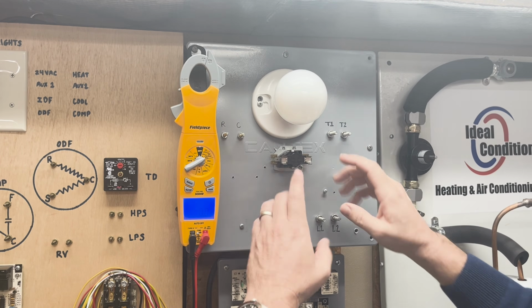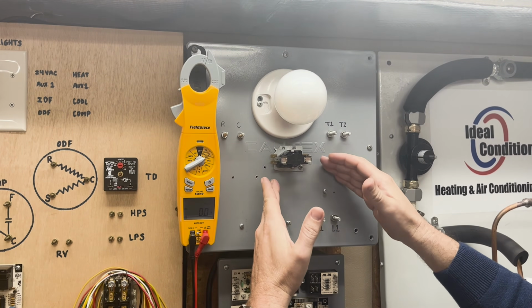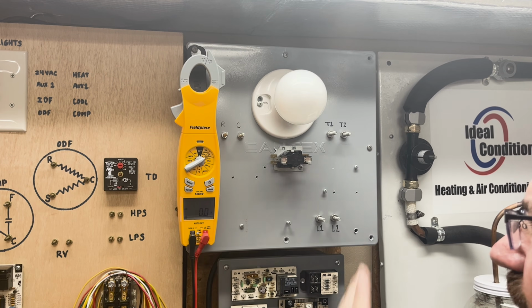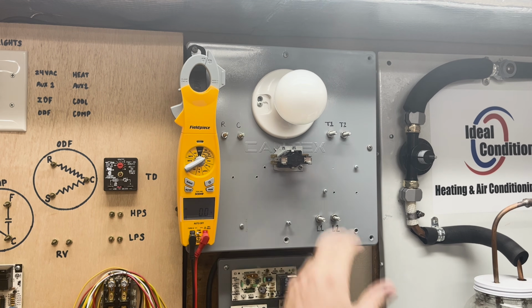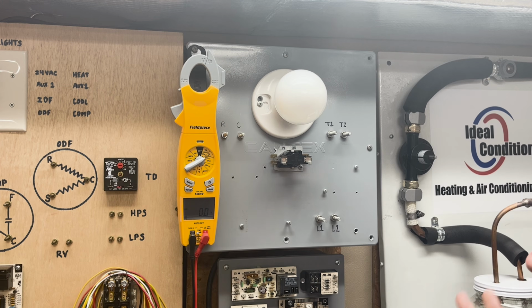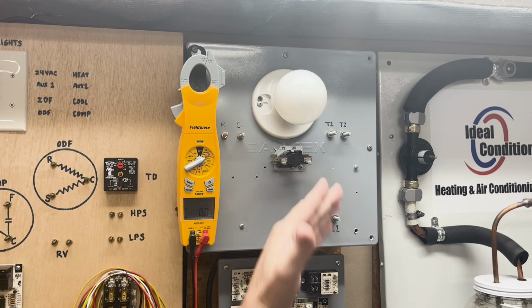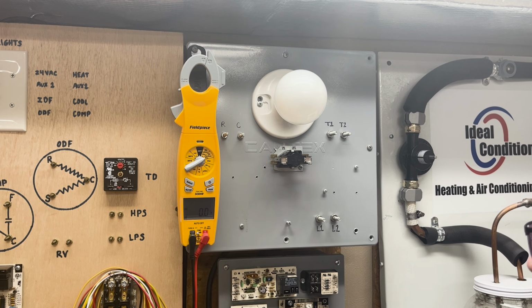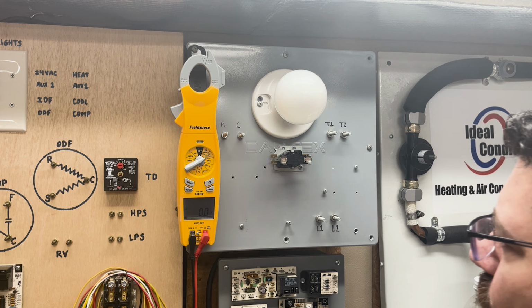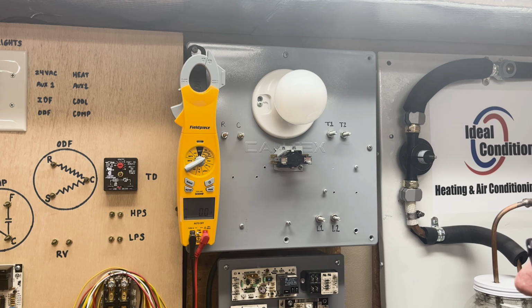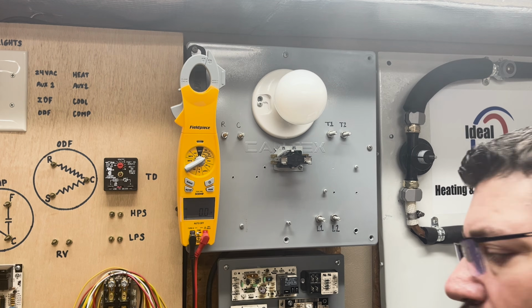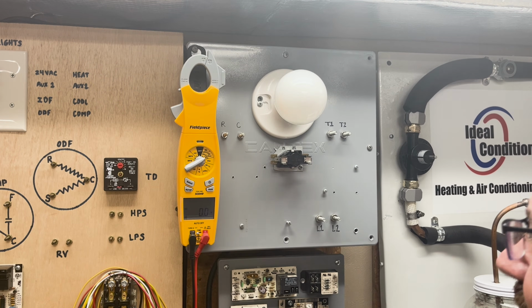Today we're going to talk about the thermal disc time delay relay, also known as a sequencer. It's got lots of nicknames. People have called it a Christmas tree because of its shape. What's important about this is it allows us to have a little bit of on delay and off delay. It's a nice integration before going to circuit boards which have that integrated into them. This doesn't require 24 volts to be present at all times to have that delay. Hence why it's called a thermal disc time delay relay.